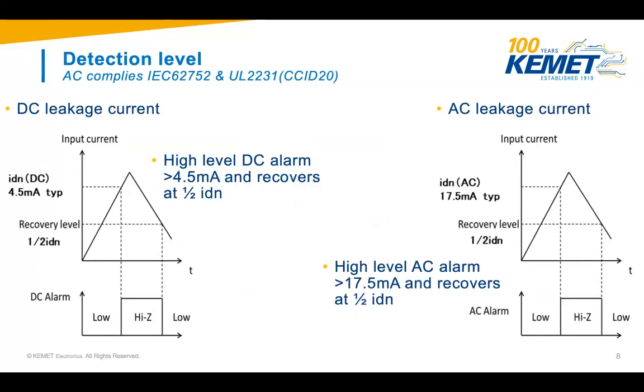You can see in the lower left corner the digital signals with a high signal that identify the DC alarm. Same concept on the AC leakage current. The typical value is 17.5 milliamps. I think on the next slide I show a table with the min and the max. In this case, it's like 15 to 20 milliamps when it starts to react. And this AC leakage current detection complies not only with the IEC 62752, but also with the UL standard 2231 or CCID 20, which this sensor is also confirmed capable of.